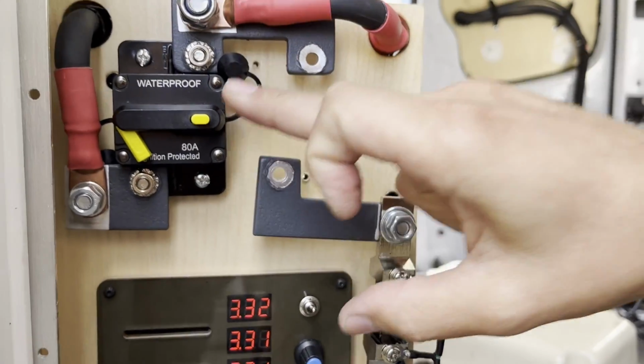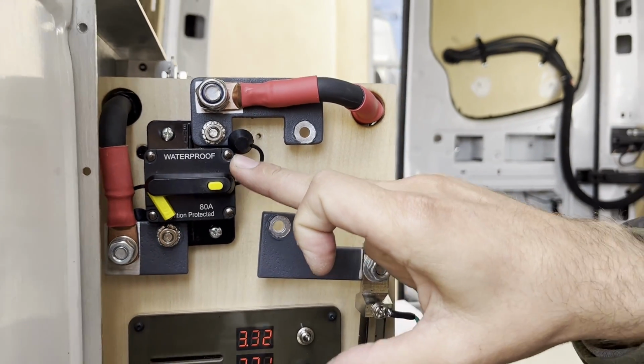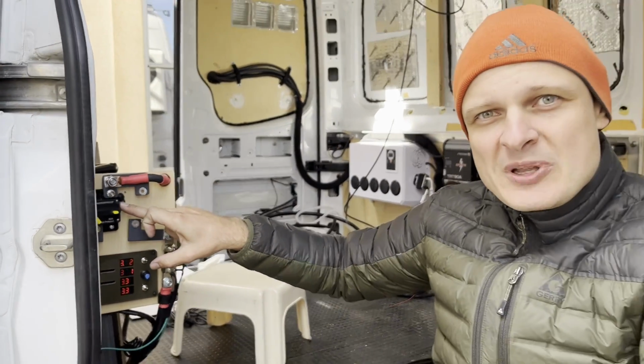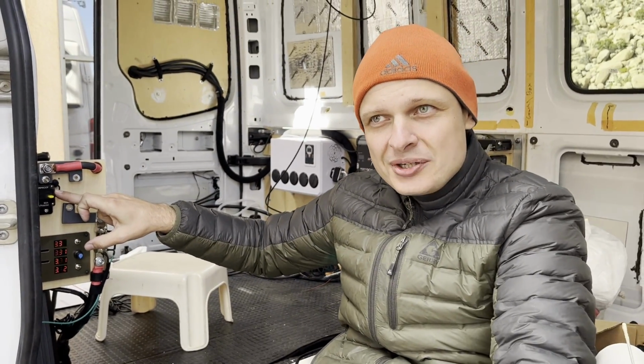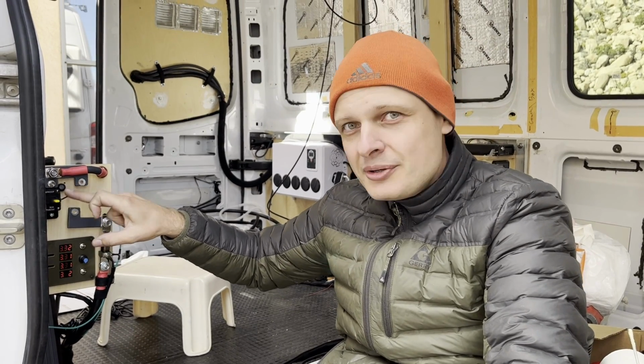But this one is an 80 amp circuit breaker. If you actually had an 80 amp circuit connected to this breaker and you start pumping 192 amps through it, you're going to have a fire. You're going to have a fire.